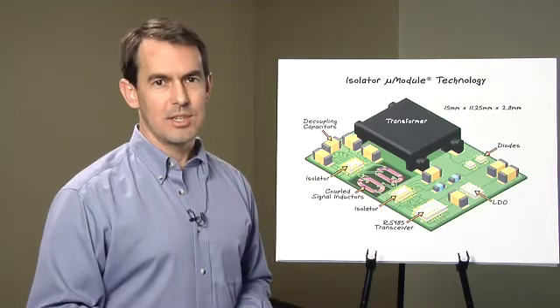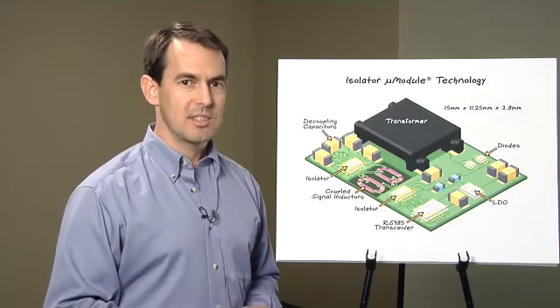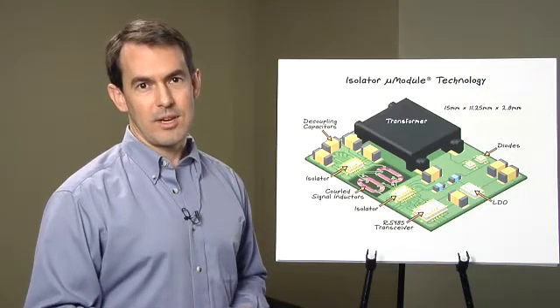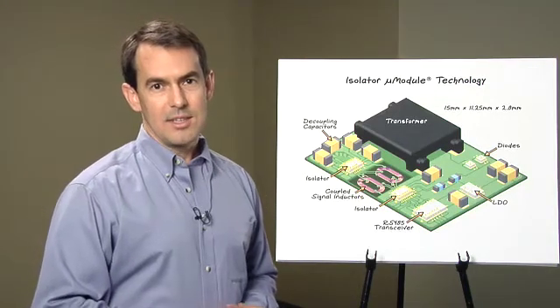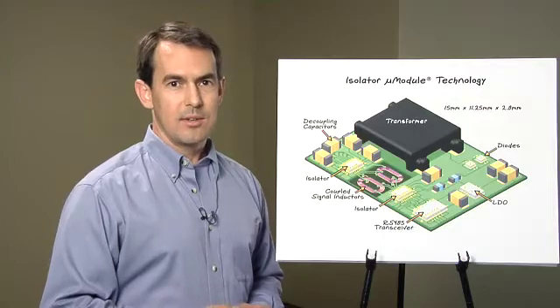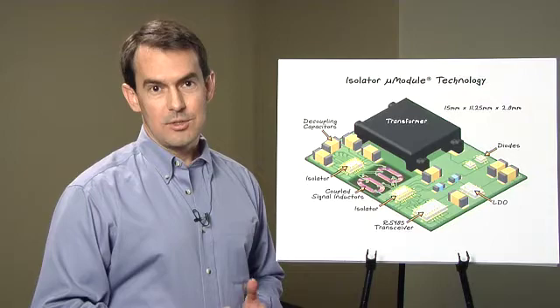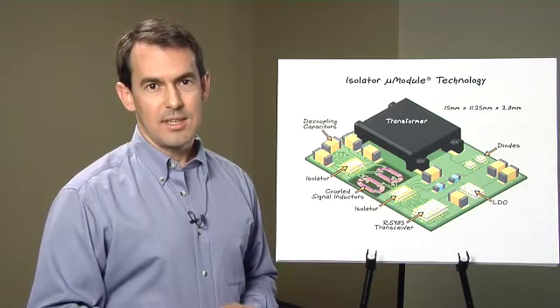RS485 is a differential signaling interface well suited to long distance communication, and the standard was designed to handle a plus minus 7 volt ground difference. Adding the isolation of the LTM2881 greatly extends the common mode operating range from 7 volts to nearly 4000 volts peak while maintaining communication.